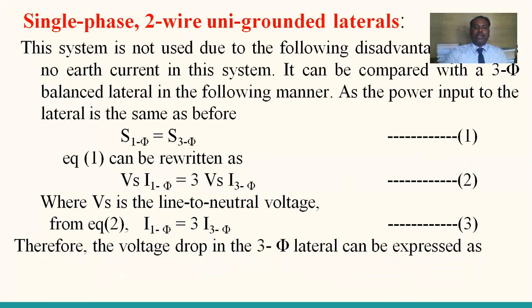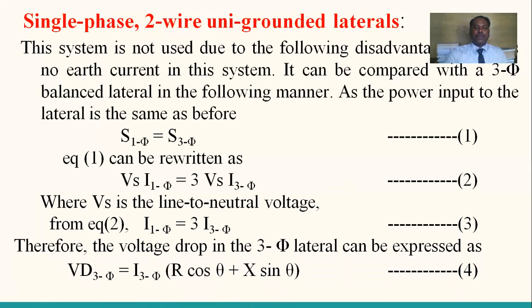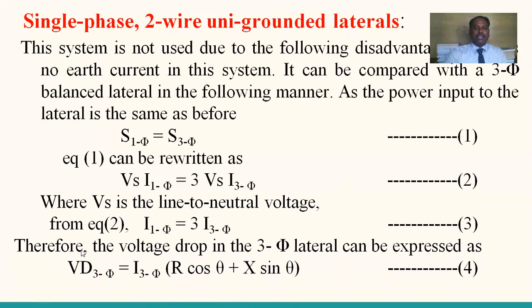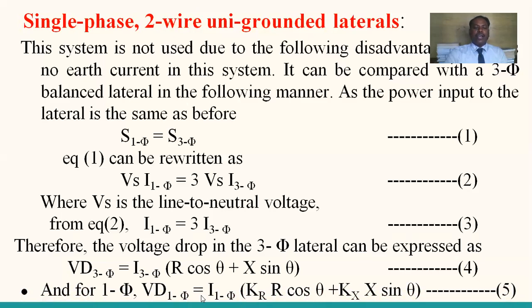Therefore, the voltage drop in the three-phase lateral can be expressed as follows. This is a familiar equation, which I already said is derived for three-phase balanced lines. The voltage drop of a three-phase system is equal to the three-phase current multiplied by R cos theta plus X sin theta. And for the single phase system, the voltage drop is equal to the single phase current into Kr into R cos theta plus Kx into X sin theta. This is equation number 5.